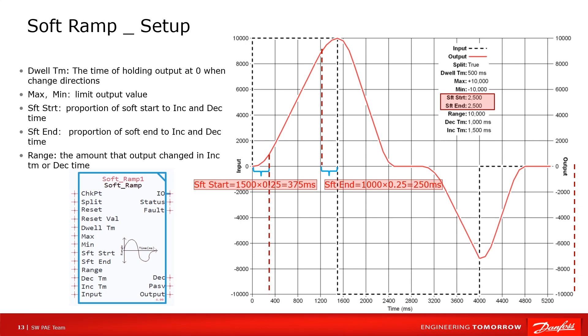As shown in the presentation, set soft start and soft end to 2500. Then soft start time should be 375 milliseconds and soft end time should be 250 milliseconds.